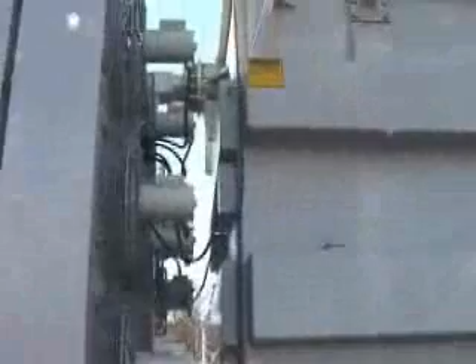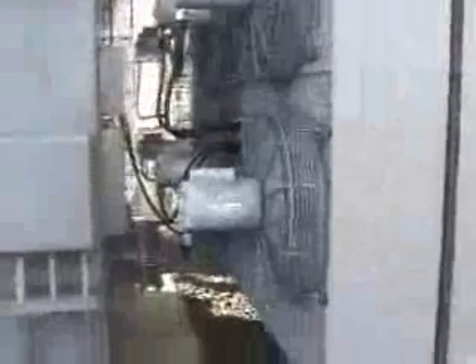This is just to see if there's anything amiss with the transformer and its construction, in case we have to notify personnel for immediate repair. One of the things we're looking for is leaking flanges, gaskets, welds, and fins. Here we're looking at the thin fins, and in some locations they can actually rust to such an extent. We're looking at the top flange here, and we can also take note of the fans to make sure they look to be in good shape.